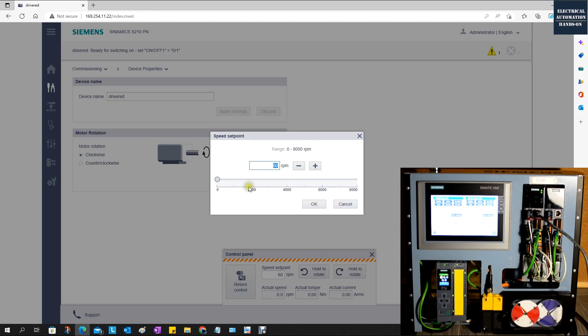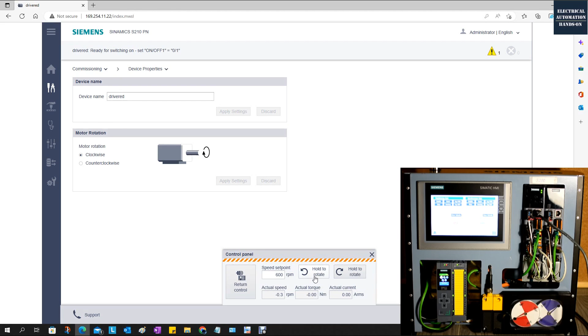Okay, if I set higher, for example, 600, hold, backward, and you will also see the torque. Okay, so this is a very great feature. We just need a minute to turn on this servo drive. As control guys, basically once the servo motor can spin, can move, can be powered up, then the rest of the things is just to do very simple parameter setting, and then you can use the motion controller technology object TO. You can power up and move the drive. You will see this is very convenient, right? Okay, now don't forget, turn off this control. Okay, and close it.